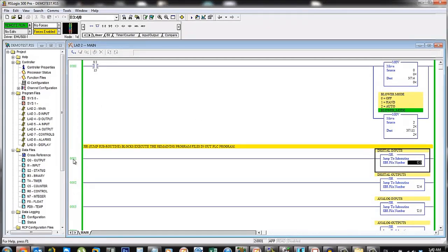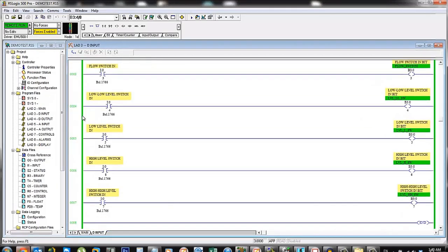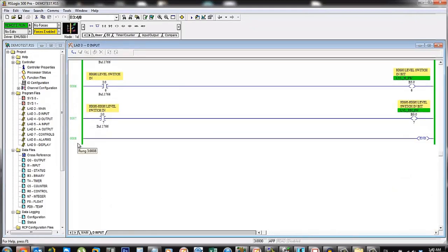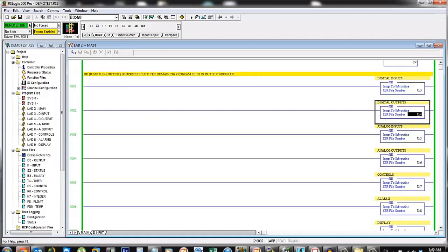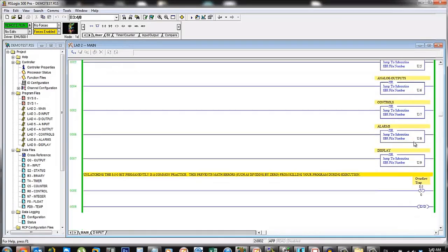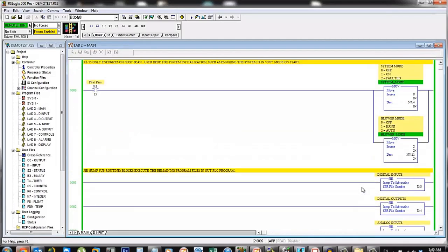So once it gets here, it's going to come over to ladder 3, and it's going to run all the way down this ladder unless it hits another jump command, in which case it's going to return to ladder 2, go down to the next line, in this case line 2, which is another jump, sending it to ladder 4, and as you can see, then it jumps to 5, then it jumps to 6, and ultimately it gets to the end and it has nowhere else to jump. So it comes right back up to 0, and it runs through the loop all over again.